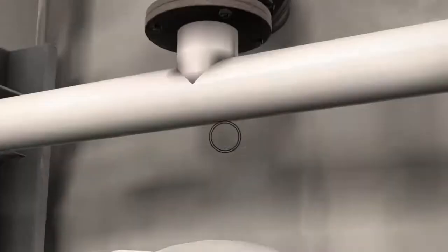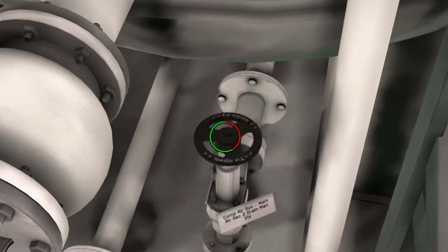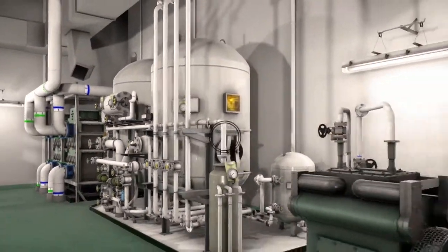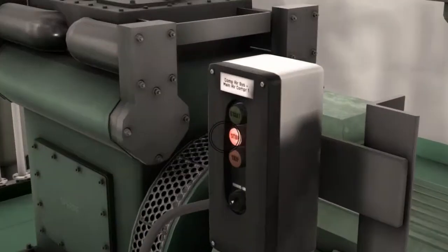To ensure that there are no contaminants in the tank, open the drain valve located at the bottom of the tank. When everything is ready, before starting the compressor ensure that there are no trip indications. If there are, reset it before starting the compressor.